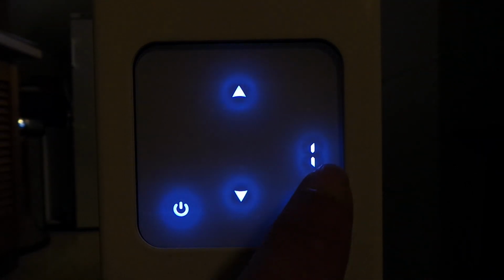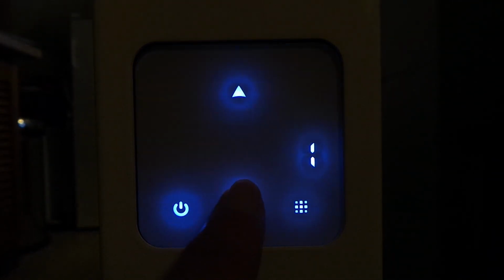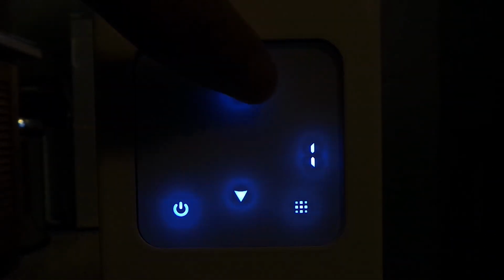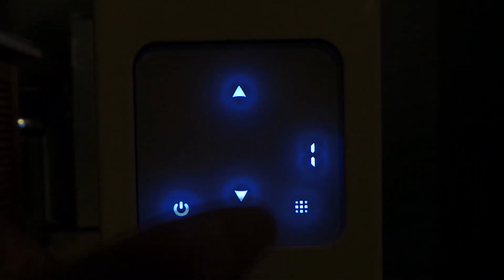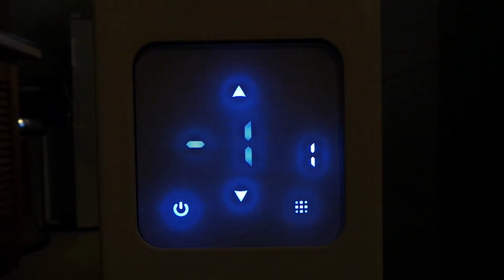We currently are looking at advanced option number 1. This smaller part of the numeric display indicates the menu option item number, and advanced option number 1 represents, according to the manual, temperature sensor calibration. That seems to have a default value of -1, and it can be changed anywhere between -9 and a maximum value of +9. So let's just set it back to the default of -1. That allows the temperature to be adjusted.